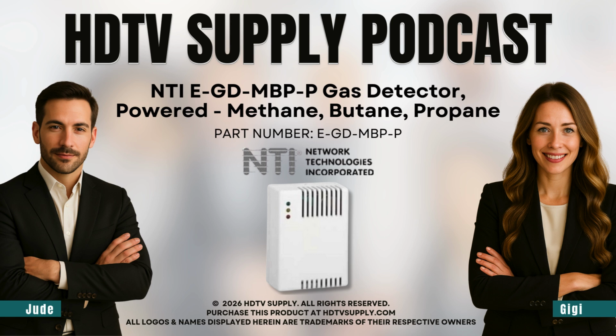Precisely. Now, level 2, that's the less sensitive setting. Okay. It raises those thresholds quite a bit. Methane detection requires concentrations over 0.8%, and propane needs to get over 0.5%. Which, of course, brings up the obvious question. Why would anyone choose the less sensitive setting? Nuisance alarms. It almost always comes down to that.